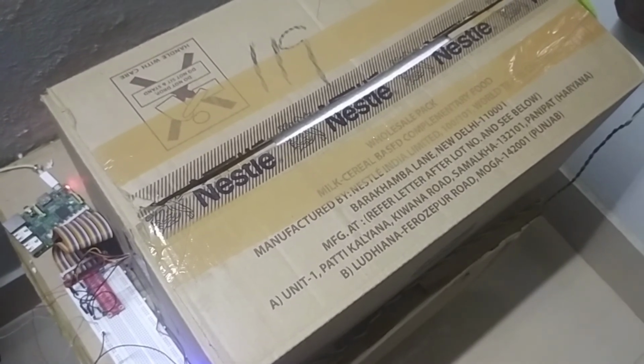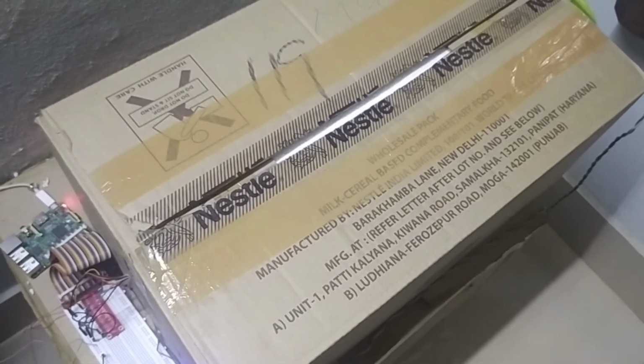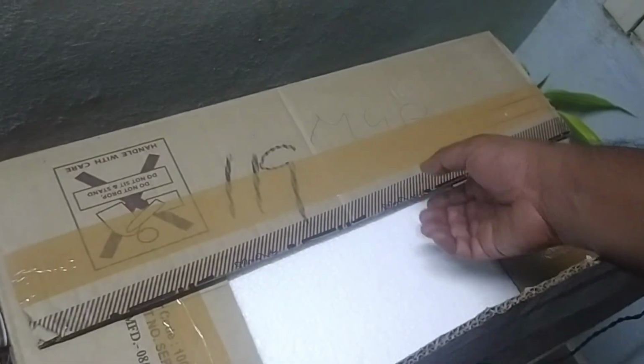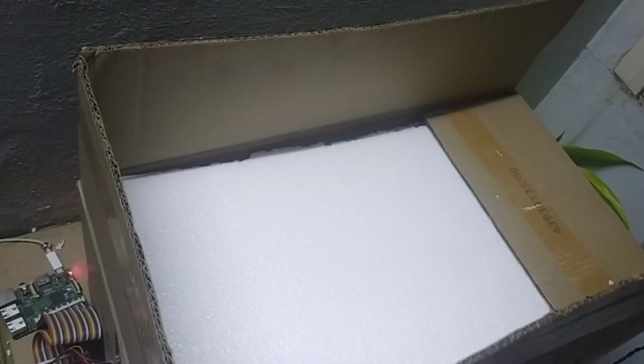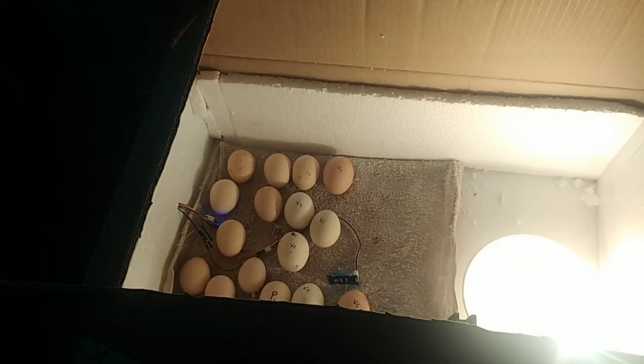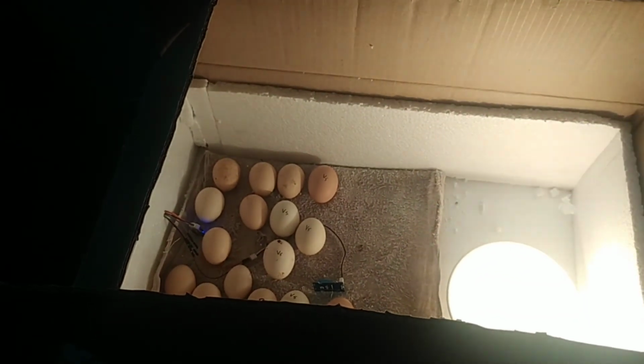In this experiment, we are going to open the incubator and leave it like that for a few minutes, and let's see what happens. Yes, I'm going to open this incubator. And I'm going to take off the insulation. And then leave it opened. What we immediately see is that this lamp is now on and will remain on, and that's because the temperature has dropped. The sensor has detected that the temperature is low, and it's turning on the lamp in an attempt to keep the temperature high. Now let's monitor what happens to the temperature and humidity after we have left this incubator open for a few minutes.